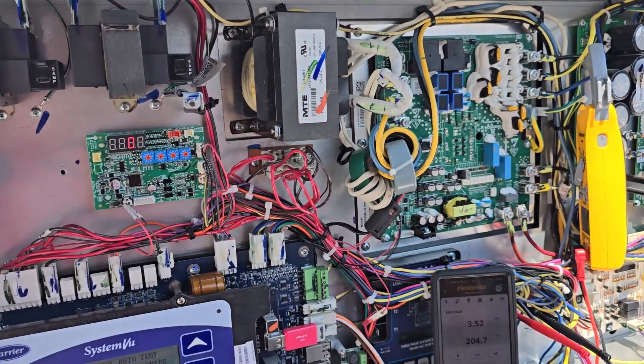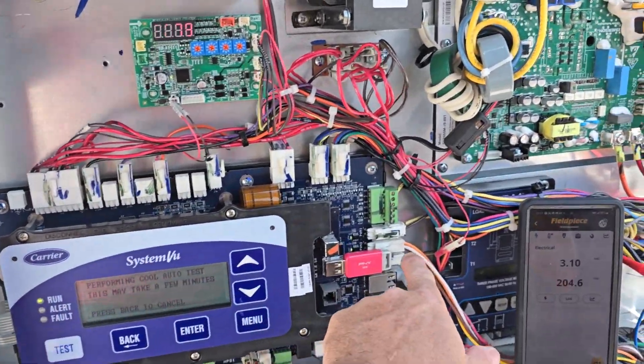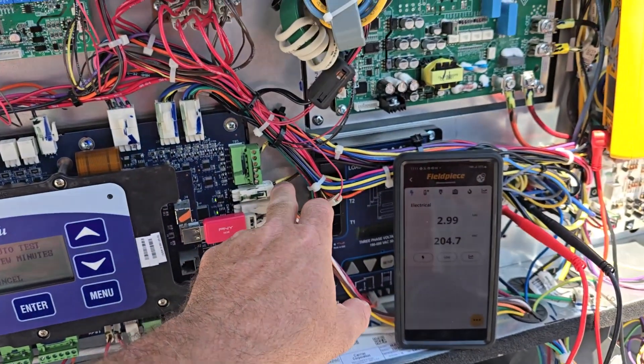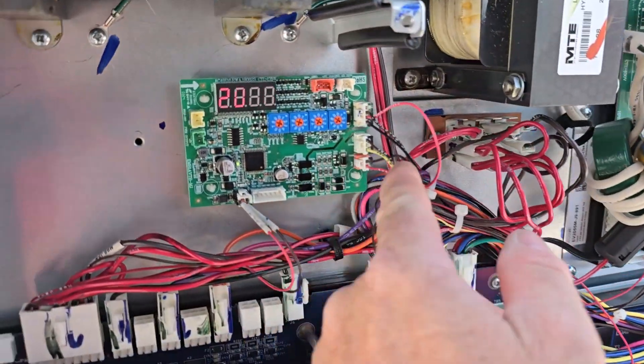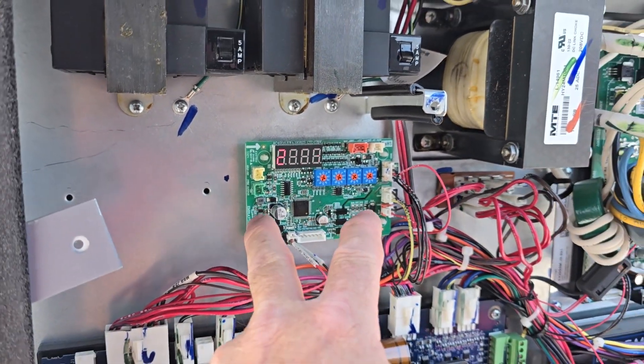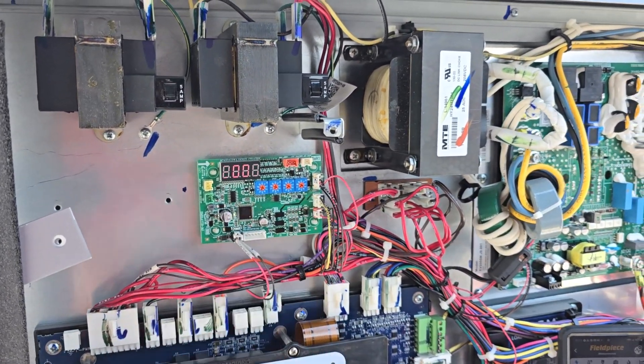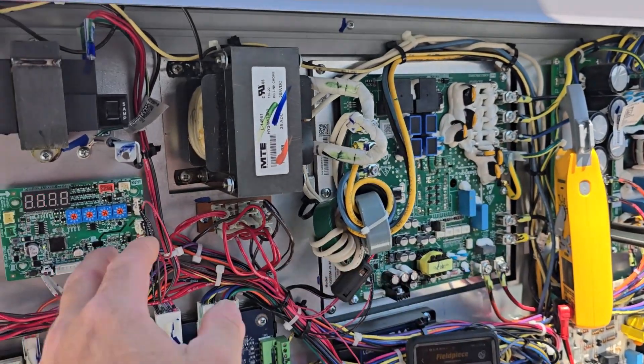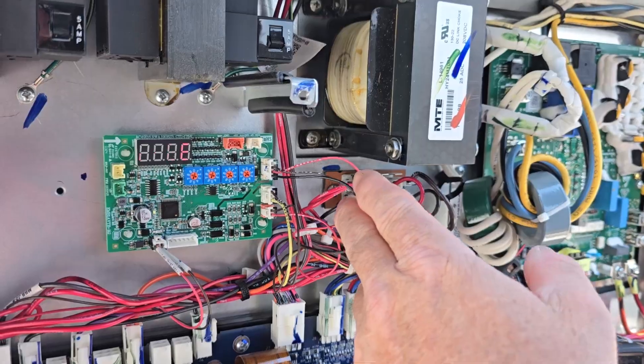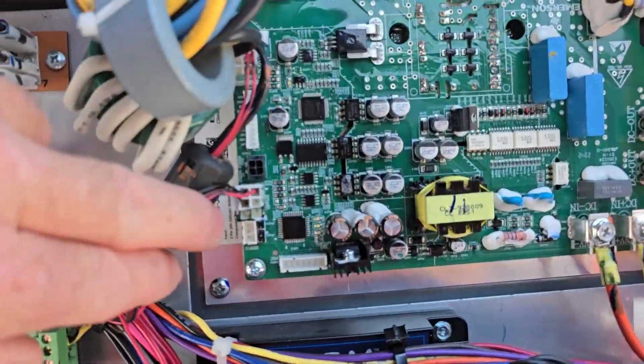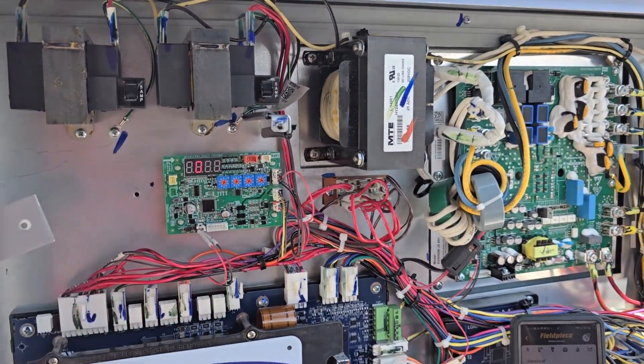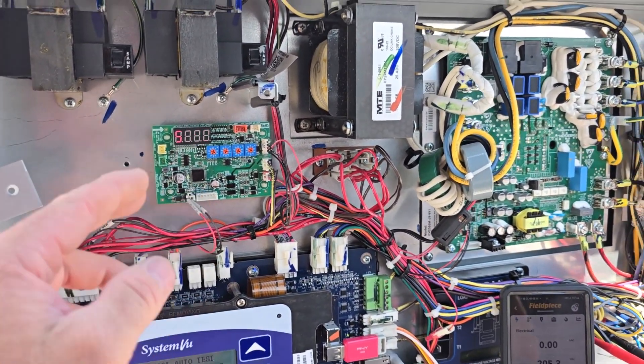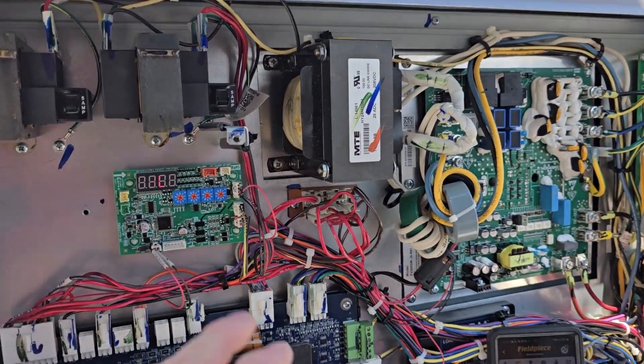So the way this works is that this here just sends a pulse width modulation out here. You can see the LEDs. One's going to the indoor fan, one's to the outdoor fan, and then you've got a two to ten, this little yellow black wire comes up here to this converter board they call it. The converter board powered up, this is what translates your speed to the inverter board. This has two-way communication, RS-485 right here, going over to right here. And so this board will serve as sending a two to ten, which this will interpret what speed to run zero to 6,000 RPM and run.